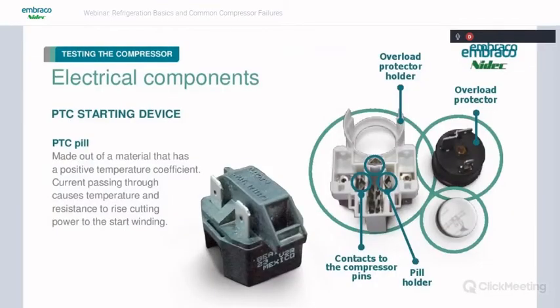Then we have the PTC relay. Like I said, it's a solid state relay, not electronic. The way this works, it has a pill made out of a material that has a positive temperature coefficient, meaning that when the compressor tries to start, it's got a low resistance and lets current pass through the start winding. Once current starts to pass through this pill, the current very quickly heats the pill up, which at the same time causes the resistance to go up, effectively cutting off current to the start winding. So when it starts, it allows current to the start winding, and in a split second, cuts it off and leaves the compressor running on the run winding.